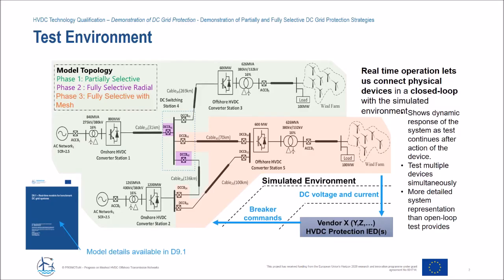So first, a little on the test environment that we used. This again was all done in real time, where the team at SuperGrid used OPAL-RT, and we used the RTDS system. But again, it's similar in that it's a closed loop simulation environment, and that lets us check the dynamic response of the overall system. It also meant that we could test multiple devices simultaneously and check that interoperability, and it's just a more detailed system representation than an open loop equivalent.